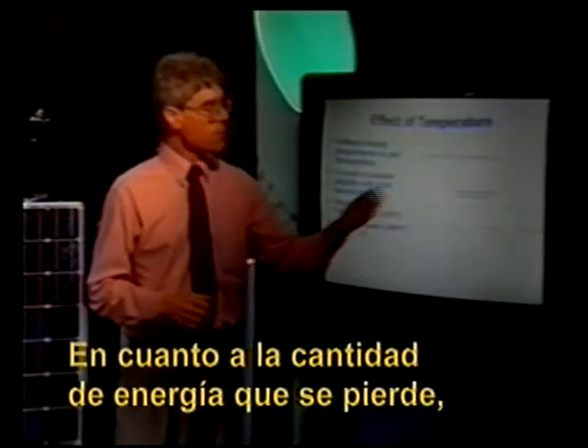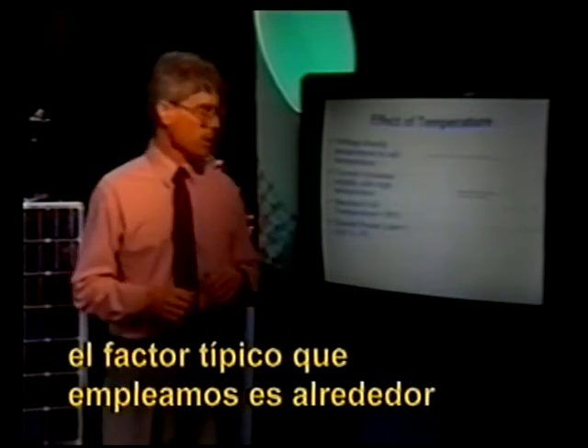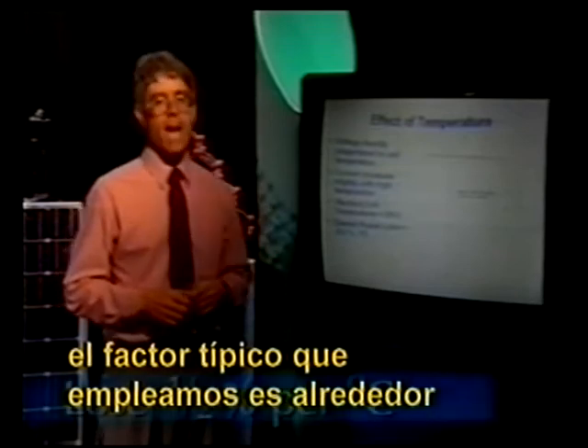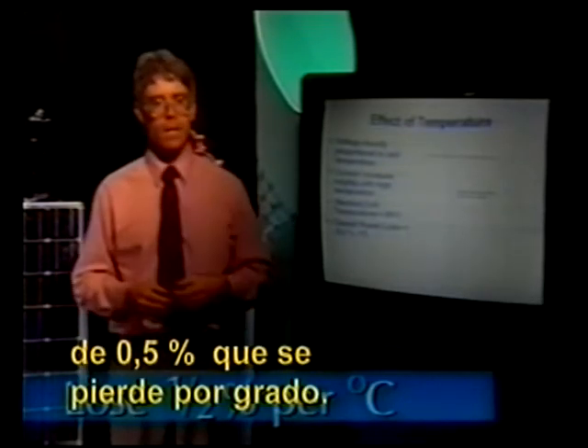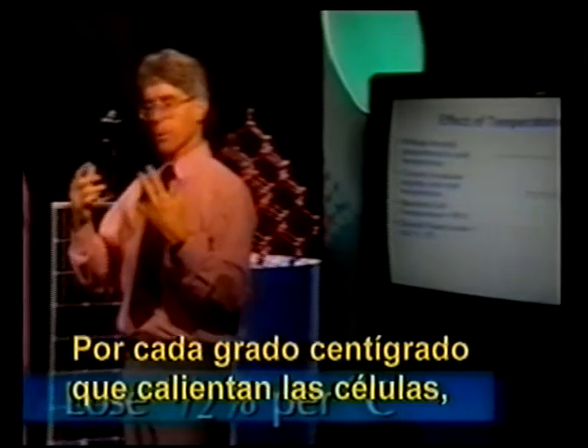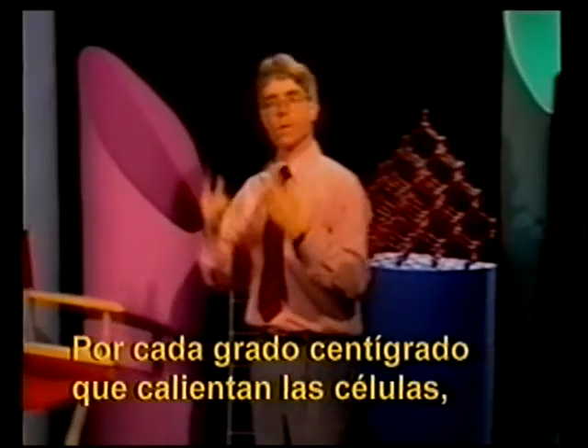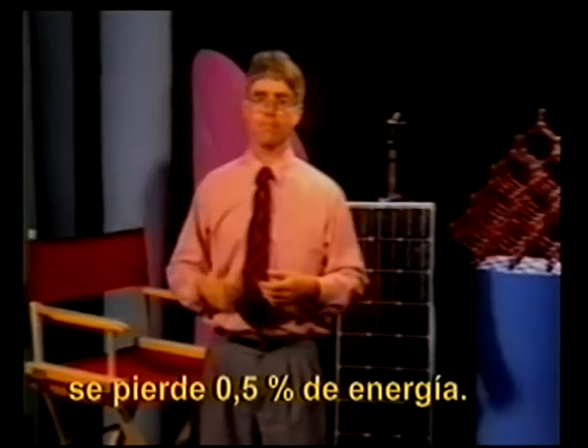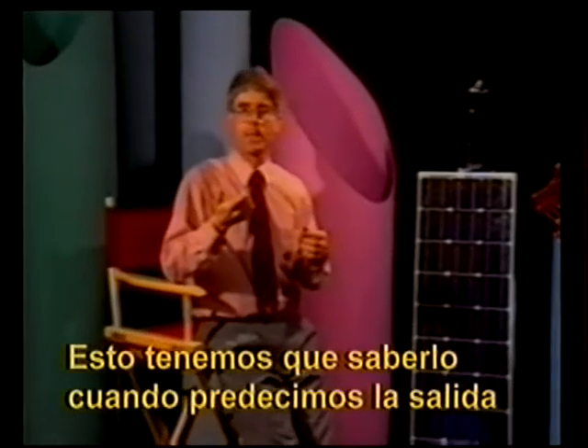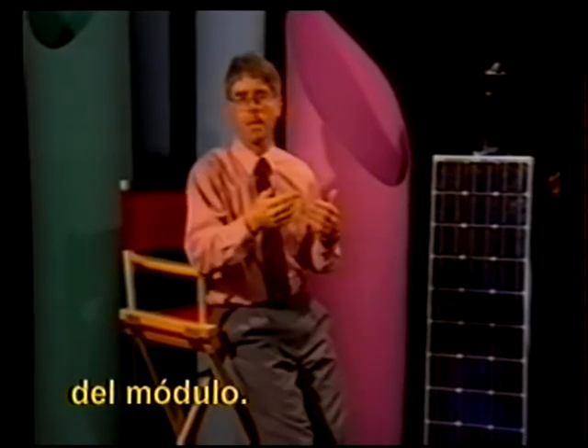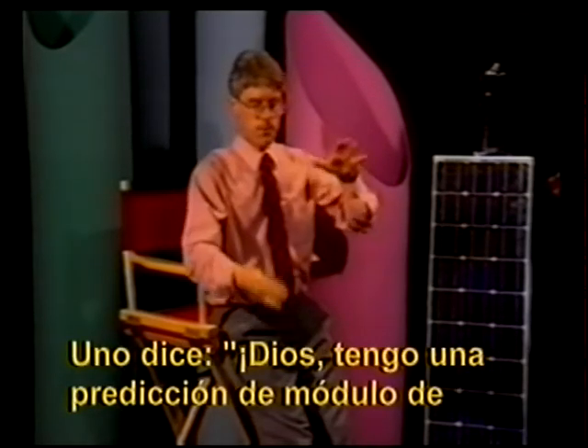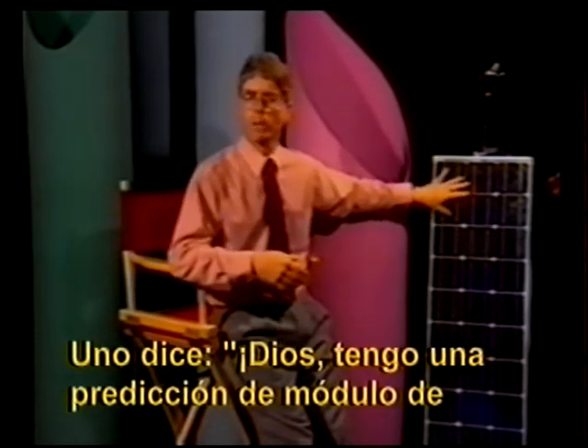In terms of the amount of power that's lost, a typical factor that we use is roughly about 0.5% loss per degree. 0.5% of your power is lost for every degree centigrade that those cells heat up. We have to know about this when we predict module output. You say, my God, you have a 53-watt module prediction here at 25 degrees.